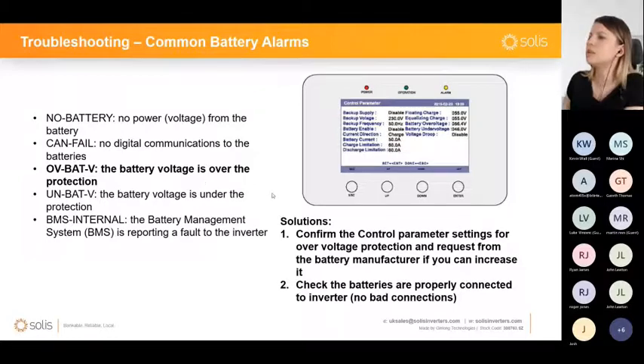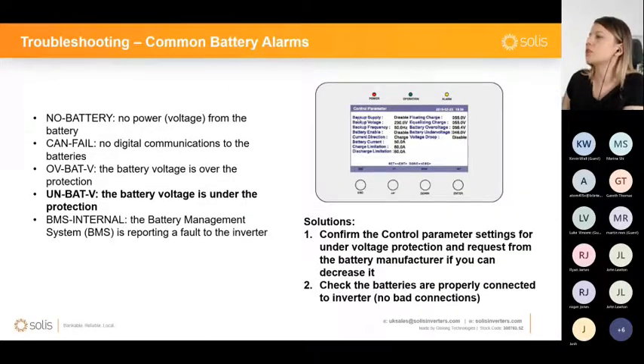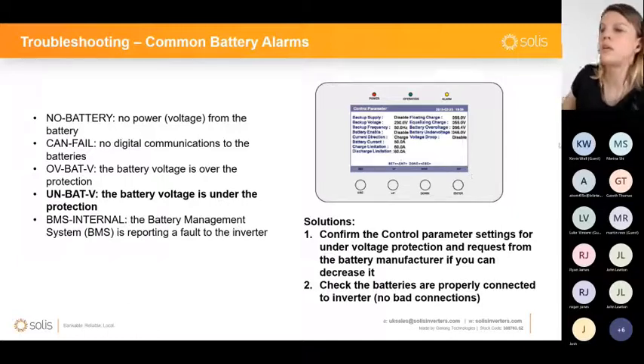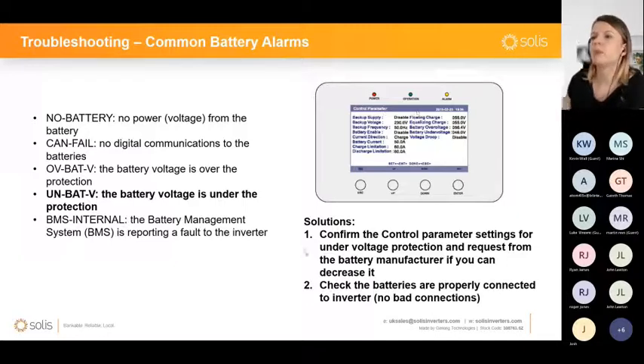Okay, yes, I was mentioning that you can see in control parameters, actually, a lot of the information from the battery settings. These control parameters, you should not change them. These are set by the battery management system. So it's not necessarily something that you can change, but you can just check and see if those values have been exceeded or not, because this is going to be an indication of why you are getting some of these alarms. And it might even help if you're checking with the battery manufacturers. It might help them troubleshoot with you the alarm on the battery itself, if it is on the battery.